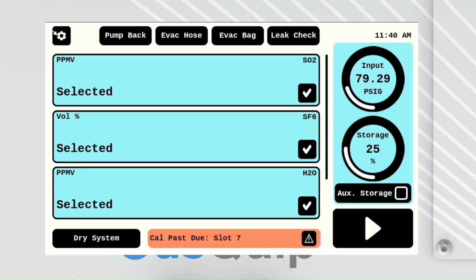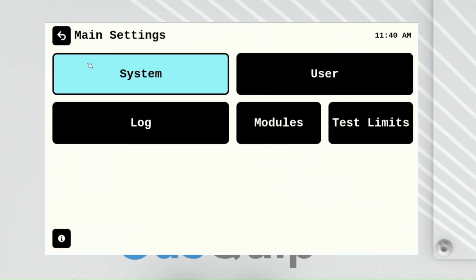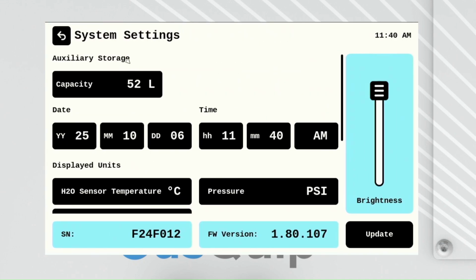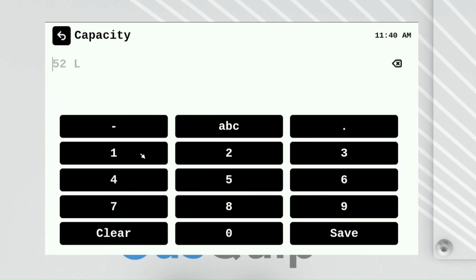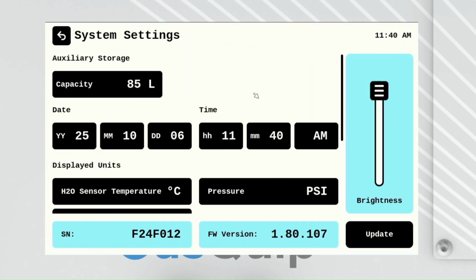Going into system settings, we'll click on the gear icon here at the top left, go into system. And the first, working from top to bottom, is auxiliary storage capacity. If we click into this box, we can set a new capacity for our auxiliary storage capacity.